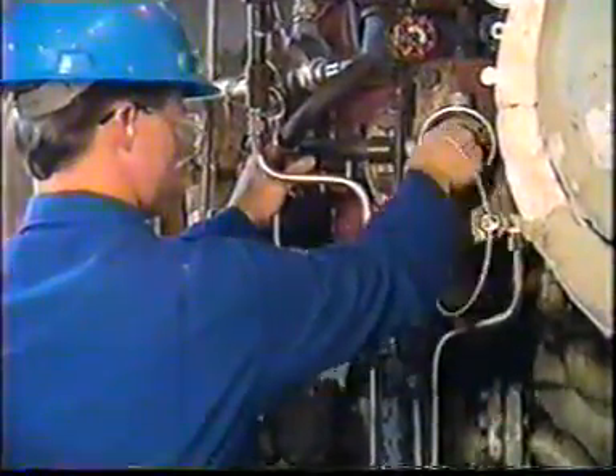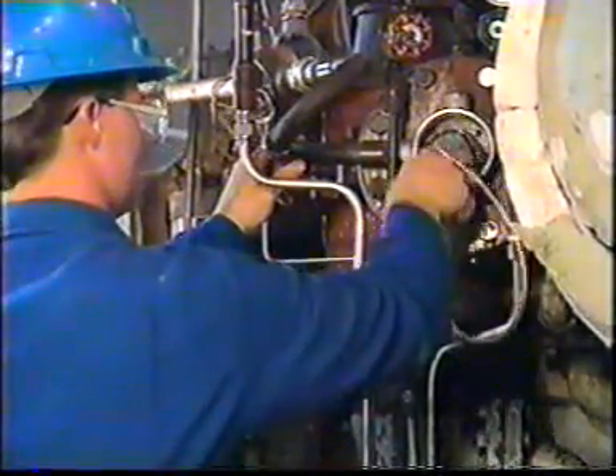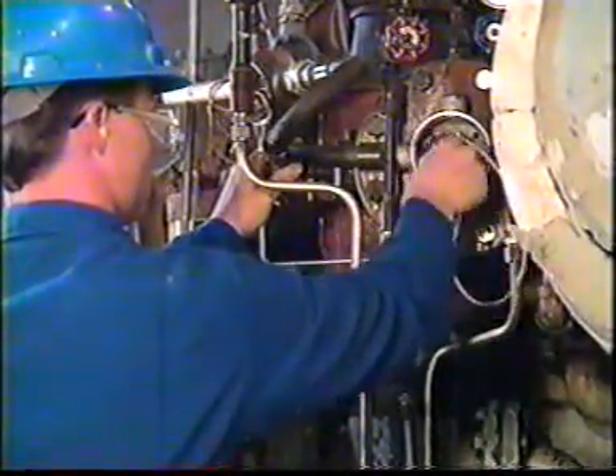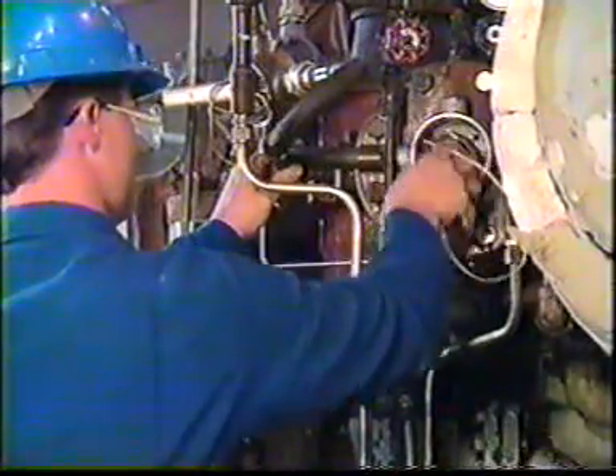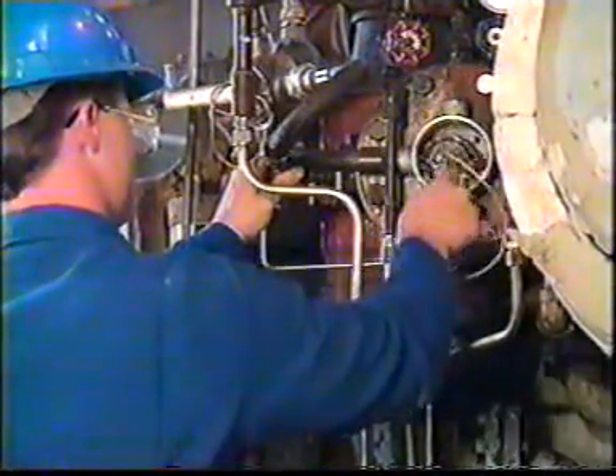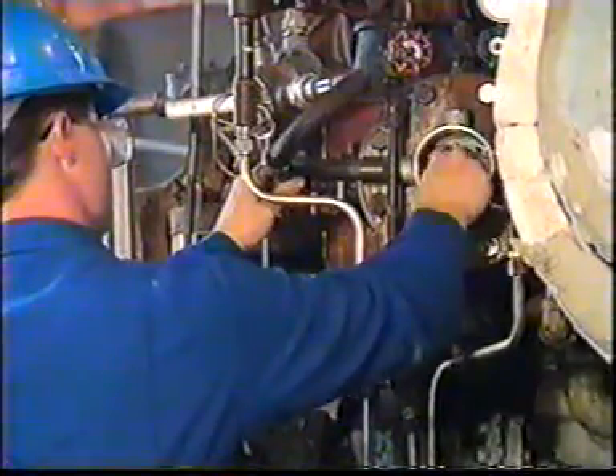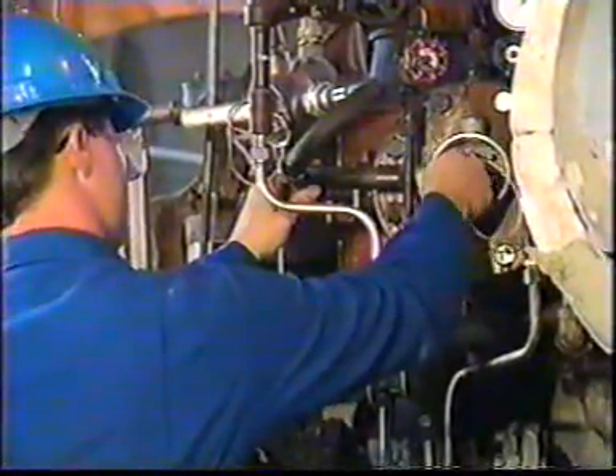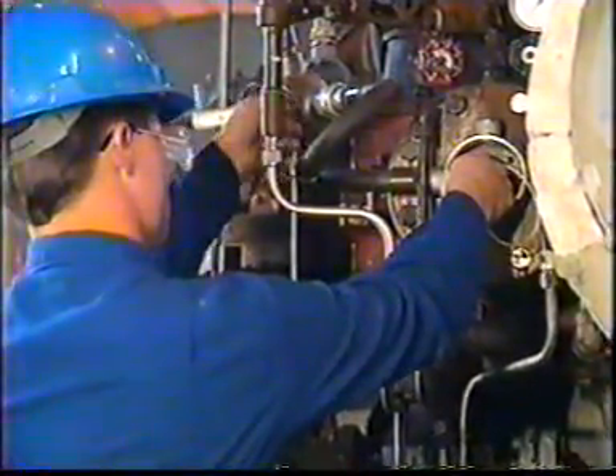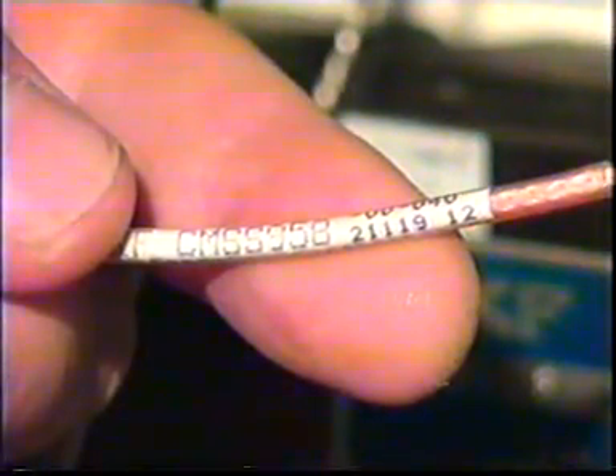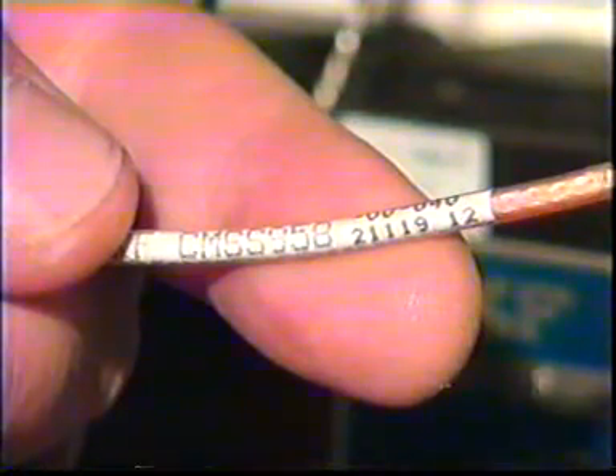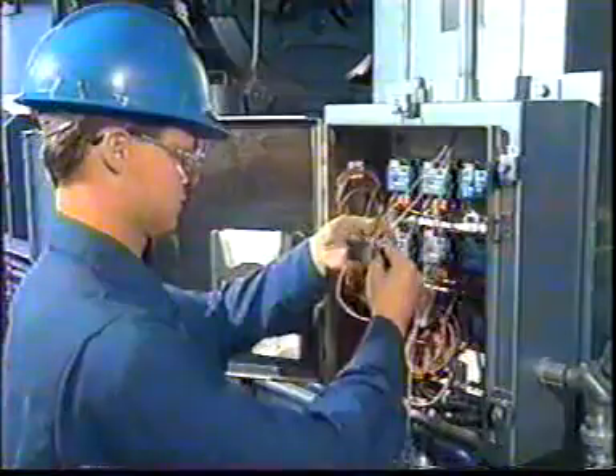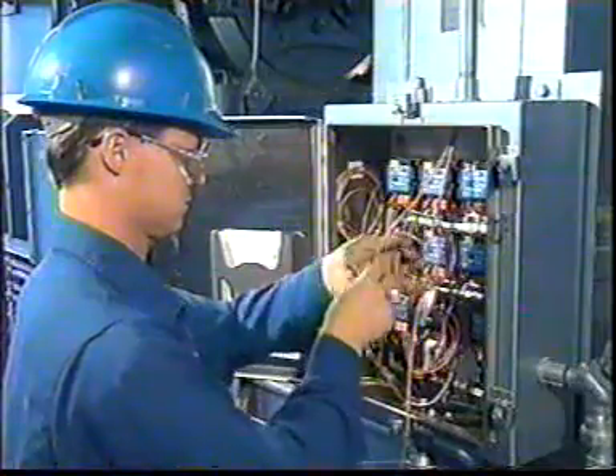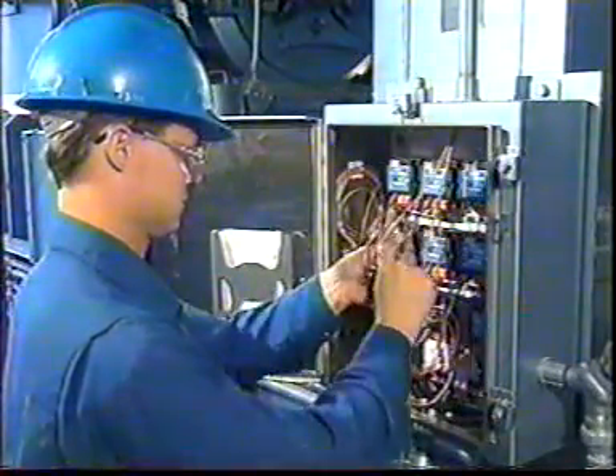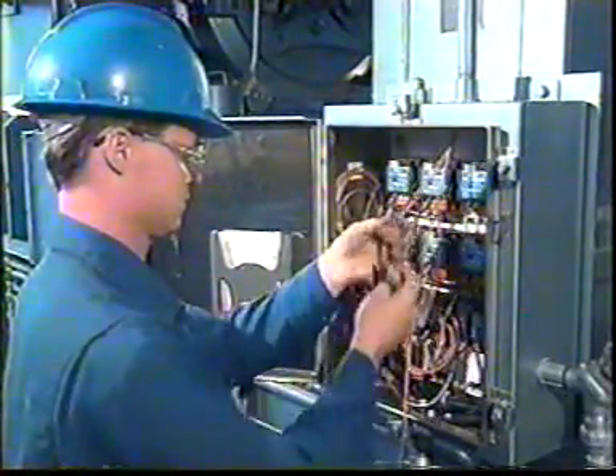In most systems, the cable length between the probe and the amplifier is critical. Remember, sensor outputs are very small. Most manufacturers provide specific cable lengths with specified resistance tolerances, and these must not be changed. If the resistance is not within the tolerance level, calibration accuracy cannot be guaranteed. Cables must be secured to prevent random movement in an electromagnetic field, which will cause a false signal.